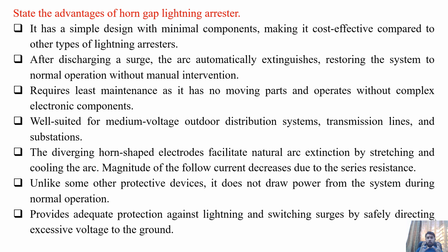State the advantages of horn gap lightning arrestor. So there are several advantages. A few of them are listed here. It has a simple design with minimal components, making it cost effective compared to other types of lightning arresters. After discharging a surge, the arc automatically extinguishes, restoring the system to its normal operating condition without any manual intervention. It requires least maintenance as it has no moving parts and operates without any complex electronic components. It is well suited for medium voltage outdoor distribution systems, transmission lines and substations. The diverging horn-shaped electrodes facilitate natural arc extinction by stretching and cooling the arc.